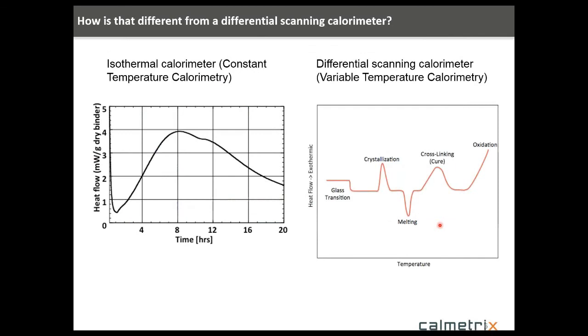One question that comes up in a lot of cases is, how does this differ from other instruments that might be in the lab, other calorimeters? On the left is shown the typical data that we get from the isothermal calorimeter. Heat flow is a function of very long periods of time, versus another instrument that you might be more familiar with, and that's a differential scanning calorimeter, a DSC. And the point is that these instruments are very different and are used for very different purposes.